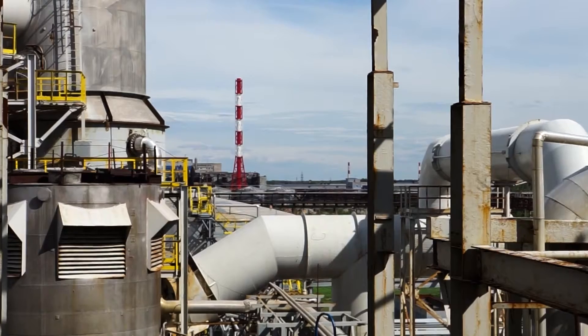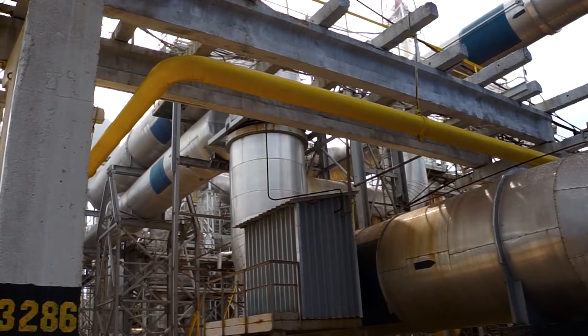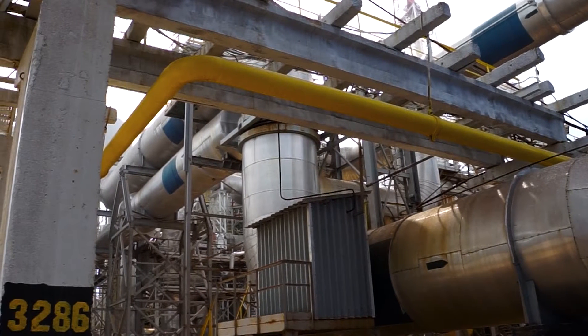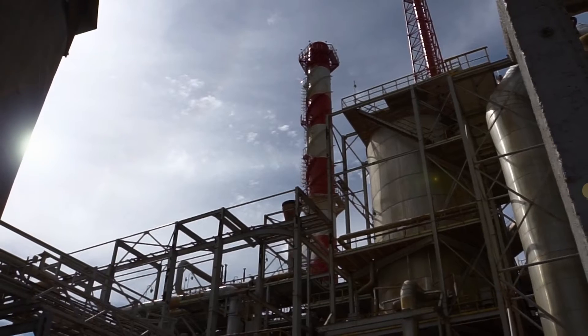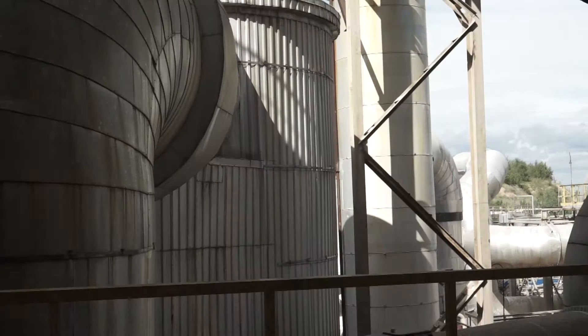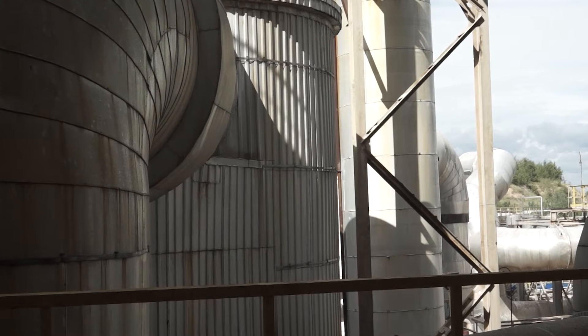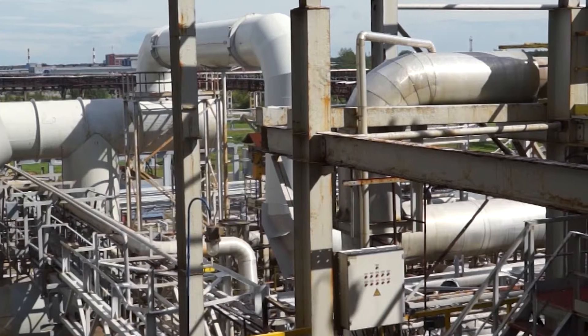we achieved an increase to the steam balance of about 70 tons of 10 kilogram steam, which is what we are currently using. During the reconstruction, we built two power units of 25 megawatt and 32 megawatt capacity, and we were able to transform all industrial 40 kilogram per square centimeter steam into electricity.